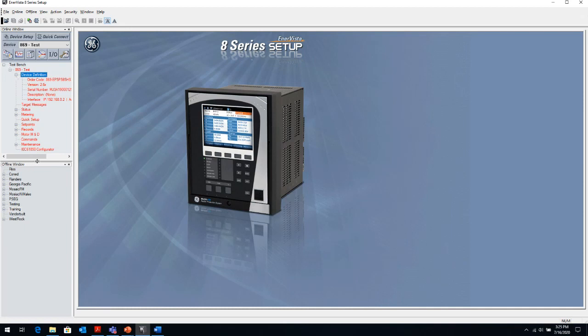Unfortunately, I don't have an 889 relay on my bench. So this is an 869, which is a motor relay. But all the 8 series follow the same convention. Whether it's an 889, 869, all the menu structures are all the same. The only difference is the type of protection that they have. Obviously, the motor protection has a thermal overload model, and the generator protection has all of the various protection schemes that we've just talked about.